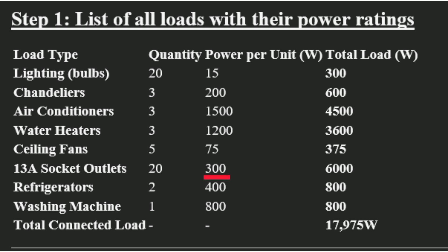We have 20 13-amp socket outlets and we assume 300 watts for every socket, so 20 of them give us a total rating of 6,000 watts. We have two refrigerators — small ones rated 400 watts each — giving us 800 watts total. The washing machine is rated 800 watts.